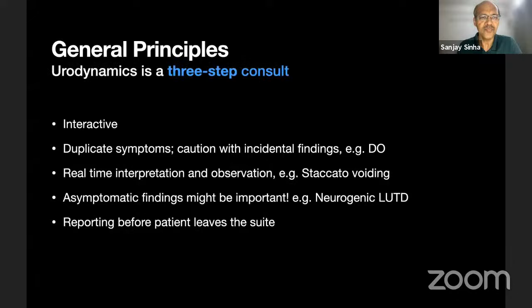So let's go back to this trace and see what the basics are here. The transducers should be zeroed to the atmosphere. So never zero the transducers to the patient, you zero to the atmosphere. And you can see when you zero to the atmosphere, there is a baseline resting pressure in the abdomen. And that varies depending on the position in which this patient is and the body morphology of the patient. These values that you see here are a good method to see whether the test you have done is likely to be a plausible test or not. So if you get values which are wildly outside this range, it would suggest that there's some problem somewhere in the way you have done your zeroing or the level at which you've kept your transducers and so on.